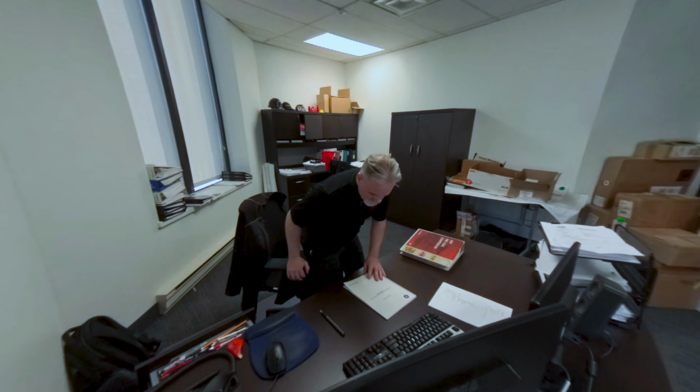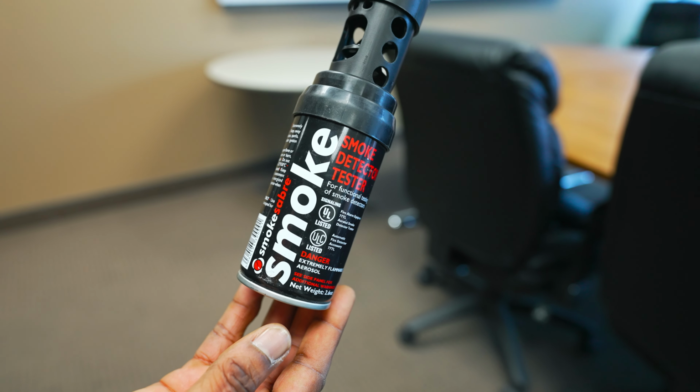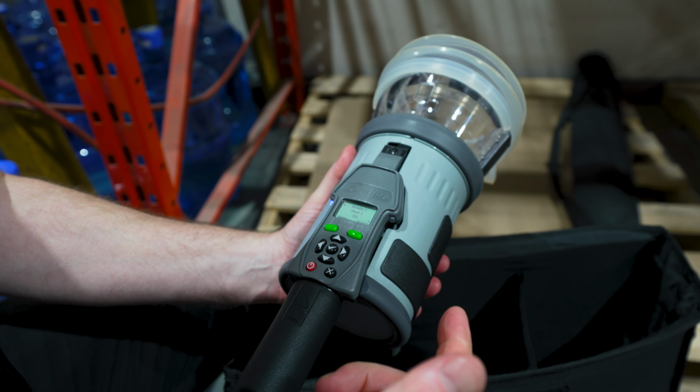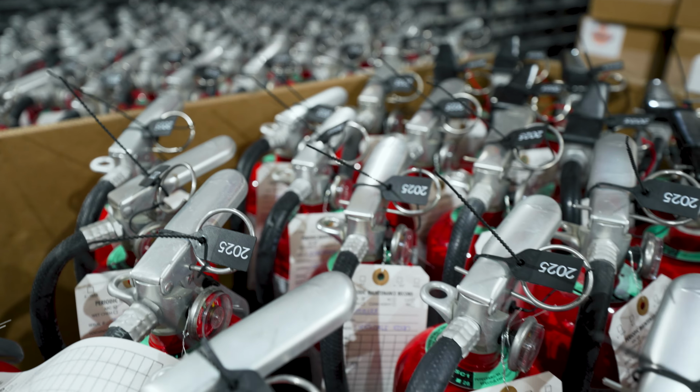So the day ahead, maybe you have your work order, you know exactly what you're going to do, find out what you need. Is there any special equipment that we're going to need? If you're doing a fire alarm manual inspection, you're probably going to need a true test, sensitivity meter, maybe something along those lines, something to test the batteries, something that's approved. That's certainly important. So make sure you have the tools and equipment that you need well ahead of time for what you're going to do at that particular facility or application.